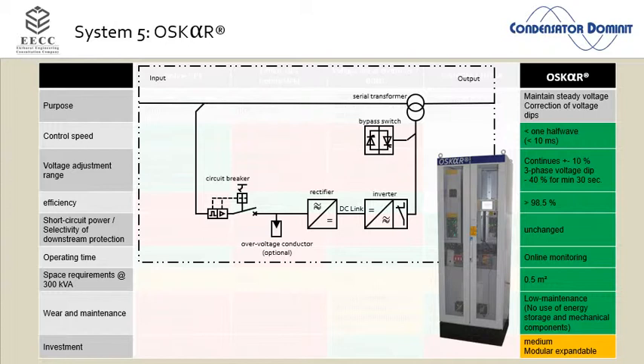But this DC link is not a capacitive energy storage, it's just a DC link. So in the moment this inverter is supplying voltage here, the DC link voltage goes down. Now we have a rectifier here, and this rectifier only knows one thing in the world, nothing else: my job is to keep this DC link at the right level, which is in this case roughly 700 volt. It's an active rectifier, so even if the voltage goes down, it's drawing actively more current out of the grid, keeping the DC link alive. The DC link supplies my inverter. The inverter pushes it into the serial transformer, and the output voltage is more or less unchanged.